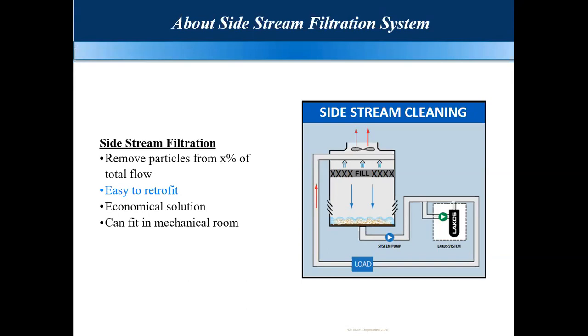Suppose the system pump or the circulation pump is 3000 USGPM. Then this separator pump will be sized to 300 to 900 USGPM. So it is an easy-to-retrofit application, and also an economical solution, because somewhere you will have, say, 10 cooling towers of 1000 TR, so the total flow rate is something near about 30,000 USGPM. You cannot have a massive system cleaning that much, right? So in that case, you can have a 3000 USGPM system, or two systems of 1500 USGPM, which keeps the system cleaner on a regular basis, right?